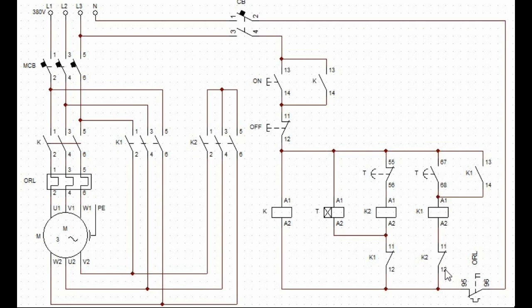Neutral is provided to contactor K1 coil at A2 from the normally closed contact of contactor K2. This process will cause contactor K2 to go off and K1 to come in, changing the star connection to delta connection.